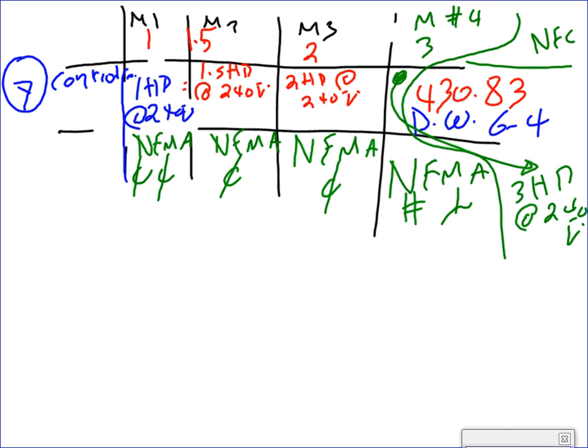Two things. Number 1, when we size the controller, we size it based on horsepower and motor, and please add also phase. We know it's phase, voltage, and horsepower, because these are single phase. And then you go to the table 430.6(A), it will tell you what the NEMA is. As you size these, you have to tell them it's single phase too, because NEMA 1 single phase is different than NEMA 1 3 phase. Can I count on you guys to remember that these are single phase? Yep. Thank you.